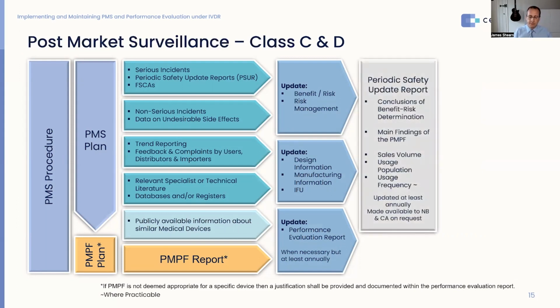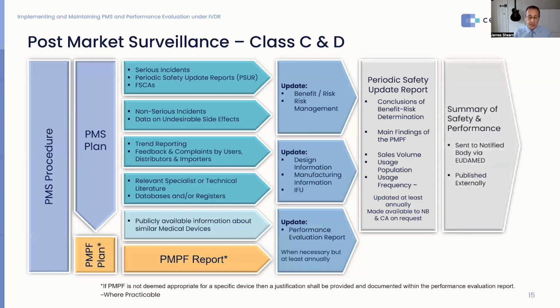For C and D, we have a different output. We have a periodic safety update report, which contains the conclusions of the benefit risk determination and the main findings of the post-market performance follow-up. It also contains information about the sales volume for the product, the population and usage frequency. That is also updated at least annually, and it's also made available to the notified body and the competent authority on request. There's an additional document, which is called the Summary of Safety and Performance. This document is sent to the notified body via EUDAMED when available, and it will be published externally. Also, if you are making Class D devices, the periodic safety update report is sent to the notified body via EUDAMED, and that way becomes available to the competent authority as well.